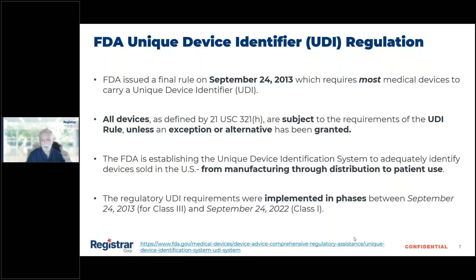The regulatory UDI requirements were implemented in phases based on the class of devices. FDA started with the highest risk class, class 3, when they came out with the rule in September 2013. One year later, all class 3 devices were supposed to have a UDI on the label. Then phased in were the class 2 devices first, the ones that are implantable or life-sustaining, life-supporting, then the rest of class 2, and then the latest step was class 1 devices, which was September 24, 2022.